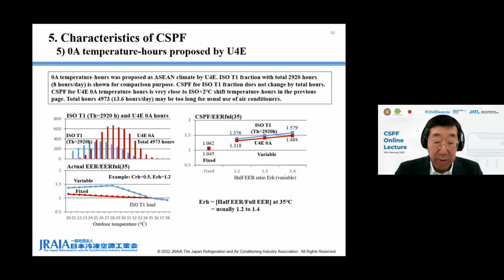This page shows the case of 0A temperature hours proposed by U4E. The upper left figure shows 0A temperature hours with total 4,973 hours and ISO T1 fractions of hours with total 2,920 hours for comparison purpose, which correspond to 8 hours per day. The lower left figure shows actual EER divided by 35 degrees C full EER at each outdoor temperature for fixed capacity and variable capacity unit. These are same for both hours.